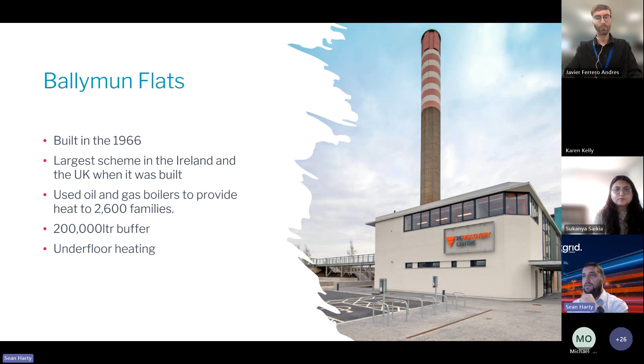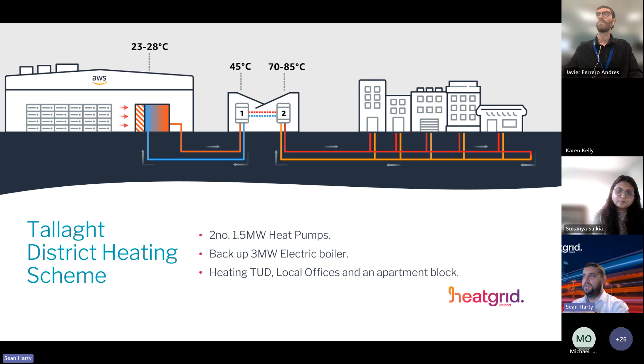This is Ireland's current district heating scheme, the Tallaght district heating scheme. It uses two 1.5 megawatt heat pumps, taking a feed from the Amazon data centre between 23 and 28 degrees. It passes through the first heat pump, bringing it up to 45 degrees, then the second heat pump brings it from 45 up to 85. It's distributed through the network, which includes the local college, a few offices, and an apartment block planned in the next few months. I know they plan to hopefully extend this as well.